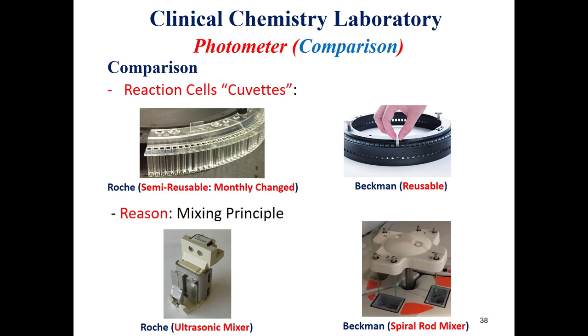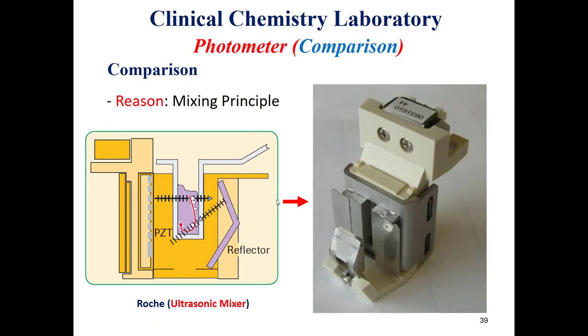This is a photo showing the principle of the ultrasonic mixer. We have piezoelectric elements, the reaction cuvettes, and a reflector. The ultrasonic wave passes through the cuvettes, which leads to mixing of the reagent and sample to have a homogeneous content. The wave is then reflected by the reflector, creating the mixing flow. This is the mixer used by Roche.